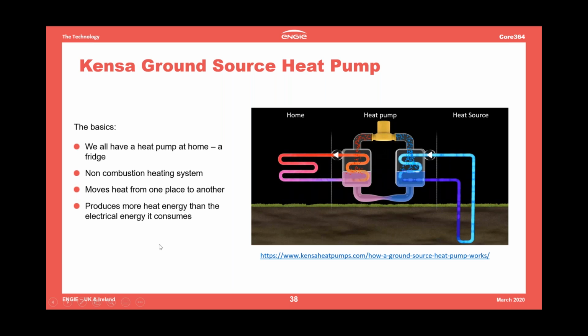The heat pump itself, inside there, we have a heat exchanger that takes the heat that's coming in from the ground, and that heat is transferred to the refrigerant fluid that's circulating within the heat pump itself. That refrigerant has a low boiling point, so even though we have temperatures coming in at only between 0 and 10 degrees, that's warm enough to cause the refrigerant to boil, and effectively we now have a gas that then goes into the heat pump itself.